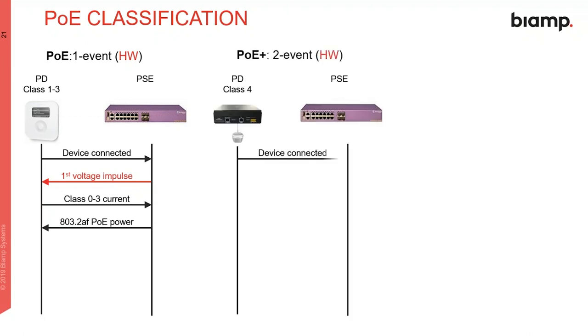If we have a PoE Plus device, we need more than that standard power, so we're going to go through that process again. We're going to have a voltage impulse after it gets connected. The device is going to give it a class 4 current to say, hey, I'm a class 4 device. Then the switch is going to turn on 802.3AF PoE power. Notice that's not the higher current at this point, so we're just providing base PoE maximum.